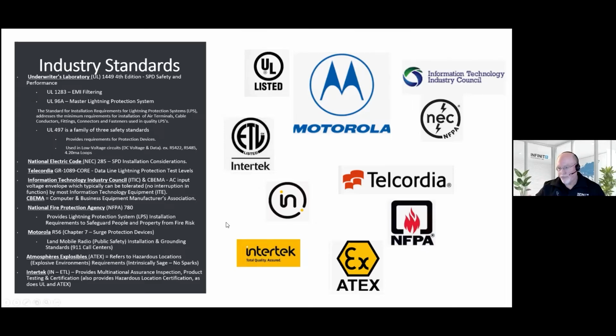And very strict. Now, ATEX is another one, along with Intertek, which refers to hazardous location certification for a surge protector. That means that if the device has been submitted for that certification for testing and it passes, then it's intrinsically safe, which means when it's operating, it will not throw a spark. And that's really critical for surge protection or electronic devices that operate around oil refineries, oil and gas fields, gas stations, anywhere where there are explosive gases. So not all surge arresters are certified to that, but if you ever see hazardous location certified Class 1 Div 2, that's what it means.